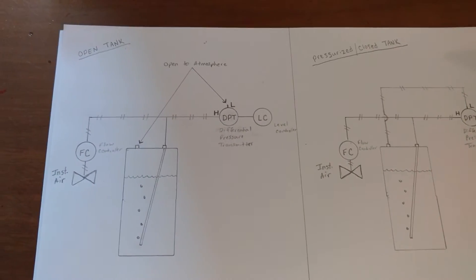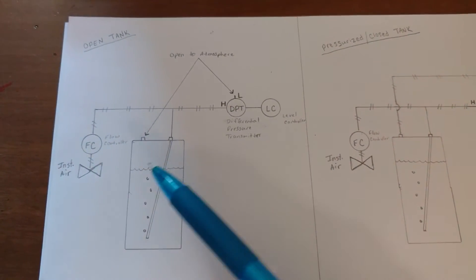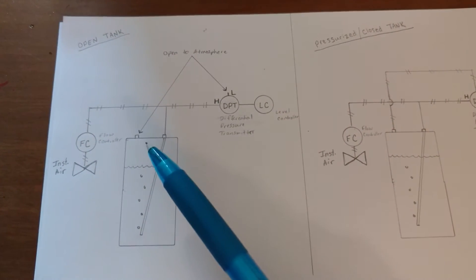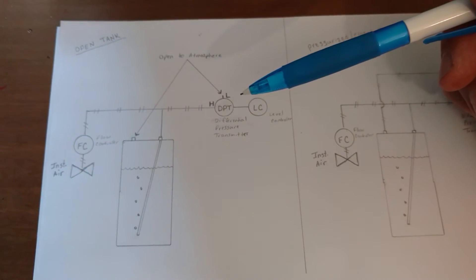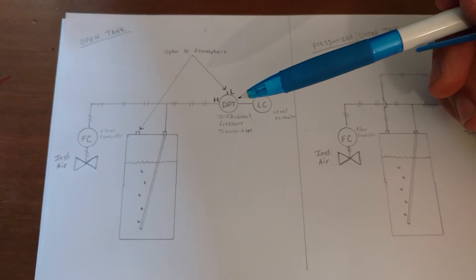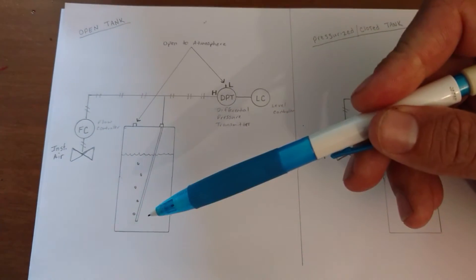So in this case, there's an open tank that's vented to atmosphere. We are using a differential pressure transmitter because we can't use a hydrostatic pressure transmitter since we don't have access to the bottom of the tank.